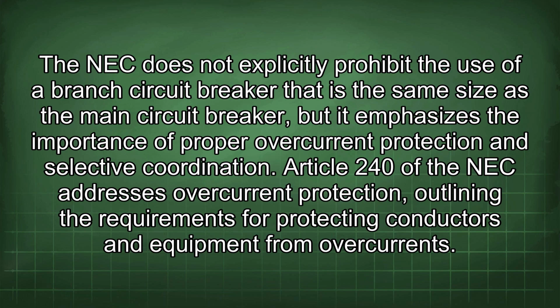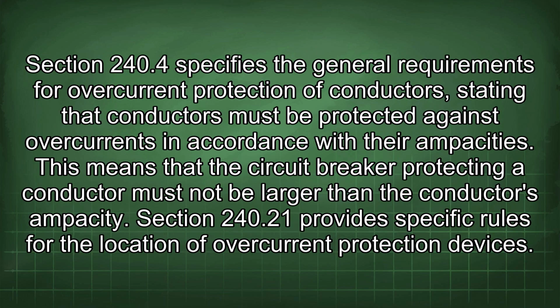The NEC does not explicitly prohibit the use of a branch circuit breaker that is the same size as the main circuit breaker, but it emphasizes the importance of proper overcurrent protection and selective coordination. Article 240 of the NEC addresses overcurrent protection, outlining the requirements for protecting conductors and equipment from overcurrents. Section 240.4 specifies the general requirements for overcurrent protection of conductors, stating that conductors must be protected against overcurrents in accordance with their ampacities. This means that the circuit breaker protecting a conductor must not be larger than the conductor's ampacity.